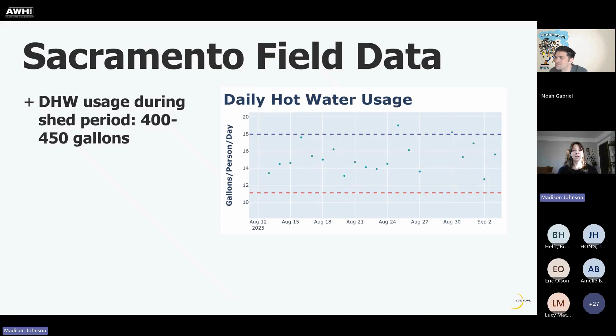And I was really hoping to be able to report the thermal shift capacity and electrical shed capacity that we're actually observing in the field. But because this installation is so new, we have a few things preventing a quality comparison. So why isn't this data apples to apples? The test data that we showed in the previous slide was operating in an advanced load up, which means the heat pump water heater was actually supplying water at an increased temperature. Instead of the heat pump producing 160-degree water, we're actually producing 180-degree water, which is higher than we tested in our single draw test. So this is going to drive different storage temperatures and different behavior.